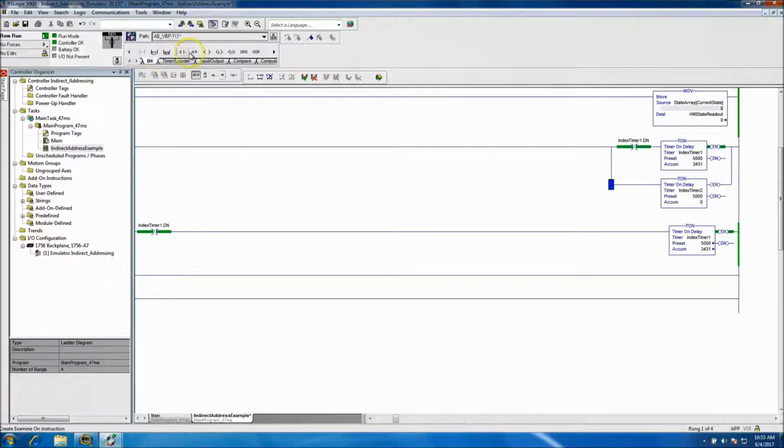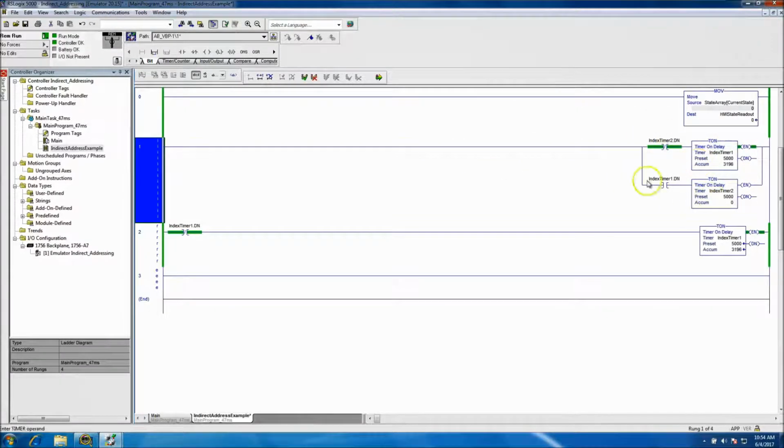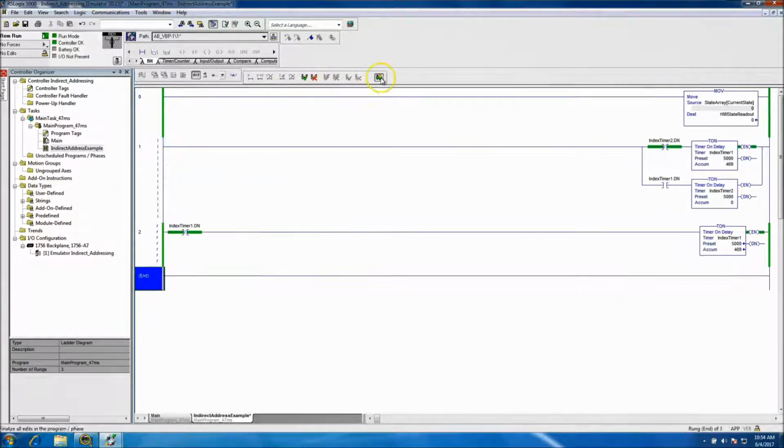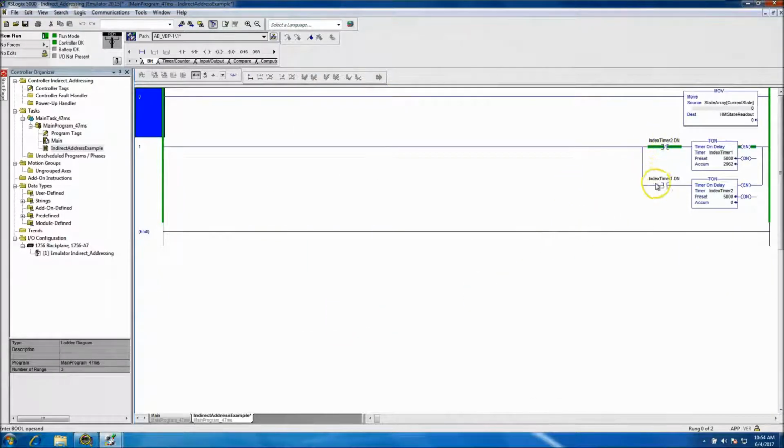And I'm doing that for the sake of, you know, I'll be able to transition everything. So what we want to do with the flasher timer, again, is just make one happen, and while the other one's happening, it basically, let's get rid of this. We want to make one bit our control bit. So as this times out, you can use this bit right here to index. So we'll shorten that up to 2 seconds. So every 5 seconds, the bit is on for 2 seconds.